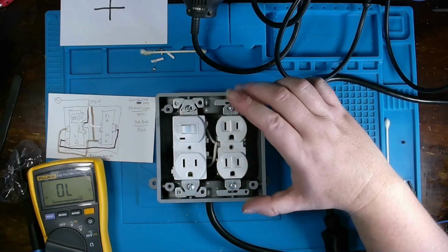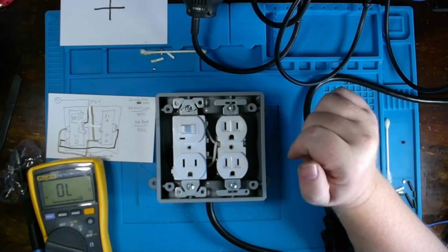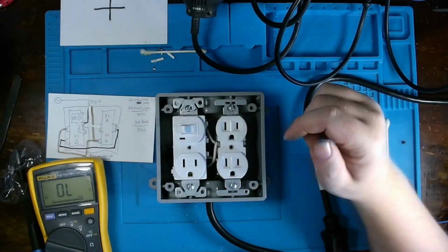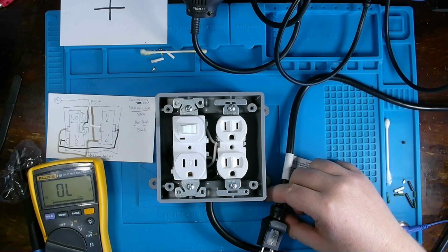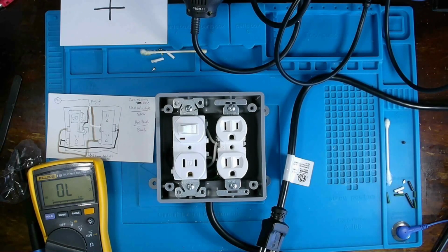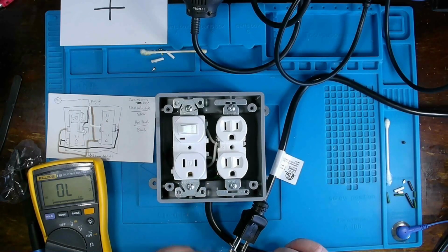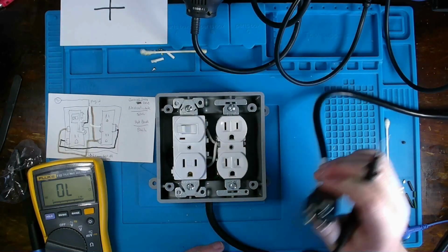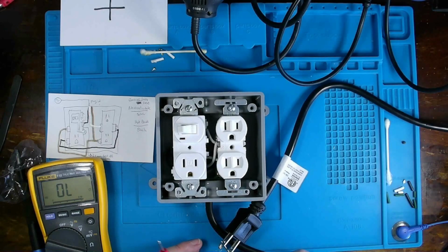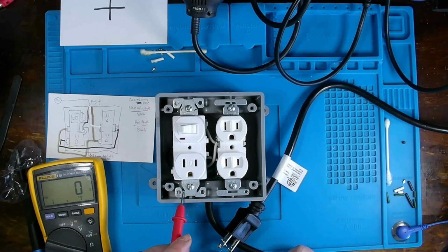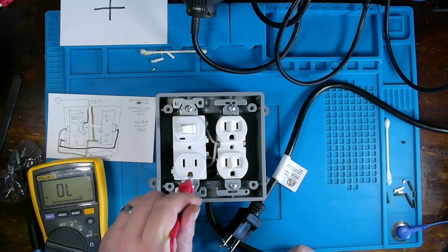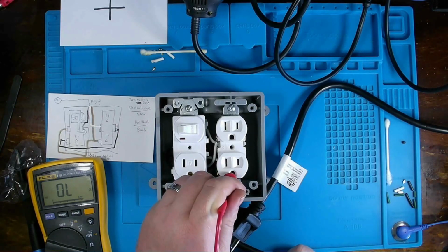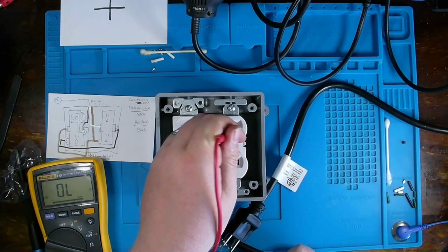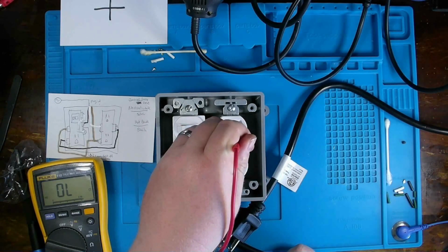Now that I have this somewhat put together, minus the faceplate and some other things, we're going to run some quick checks. First one's going to be a continuity test of all of our grounds. So while touching the ground lead on my plug here, I should have ground to these tabs, as well as internal on these plugs.